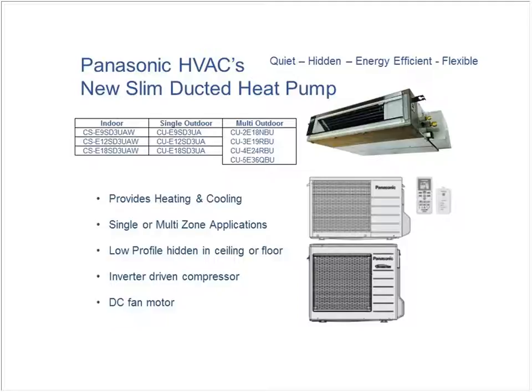So as far as I'm concerned, for fresh air, to move fresh air, this is by far the best application. It just costs more money. Because now I can put air at temperature, at the demand temperature, fresh air at demand temperature into the room. It'll be dehumidified and filtered before it gets there because it's coming through the ERV, HRV.